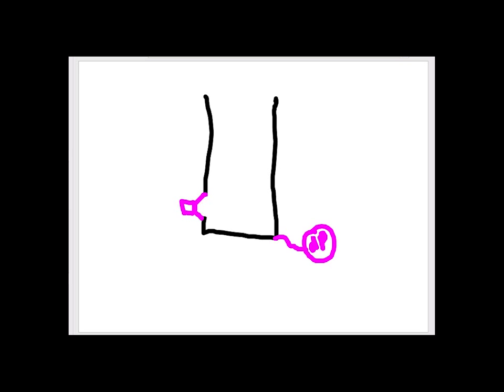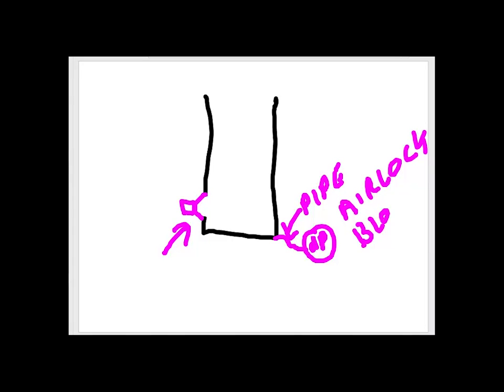Nowadays, with ceramics, I would certainly advise you to use a flange-mounted DP, because any pipe that we have connecting is a maintenance item - it will get an airlock sooner or later, or block. So with the state of reliability of ceramic pressure sensors today, I would say flange mount onto the tank. You'll never get an airlock, it'll never get blocked, and if it does ever get dirty, the operator can clean it with a hose.